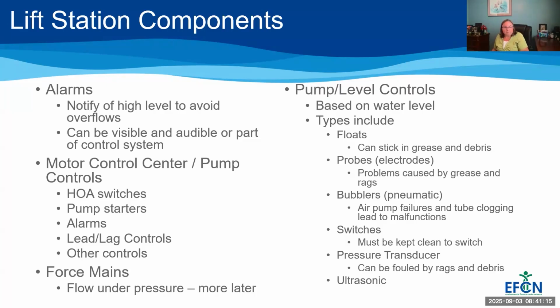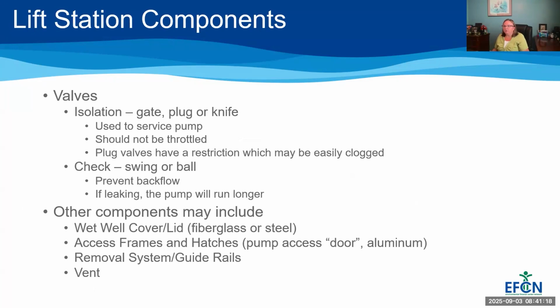The next components we're going to talk about, your valves. You typically have a couple of kinds of valves in a lift station. You have your isolation valves. These can be gate, plug, or knife valves. They're used to service your pump. So if you need to pull your pump, you would close your isolation valves and pull your pump. They should not be used for throttling. Throttling valves in lift stations can create all kinds of problems, and so it's discouraged. I know that sometimes we do it anyway, sometimes we have to do it, but if you're throttling a valve, it probably means that you've got a bigger issue, and something should be changed. The pump should maybe be changed because the flow rate's changed, anything like that.